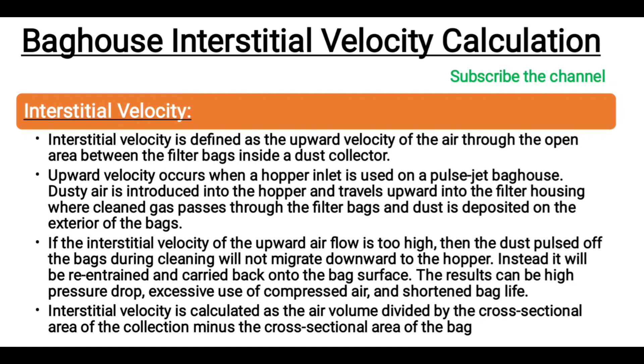Interstitial velocity is defined as the upward velocity of the air through the open area between the filter bags inside a dust collector. Upward velocity occurs when a hopper inlet is used on a pulse jet bag house. Dusty air is introduced into the hopper and travels upward into the filter housing, where cleaned gas passes through the filter bags and dust is deposited on the exterior of the bags.